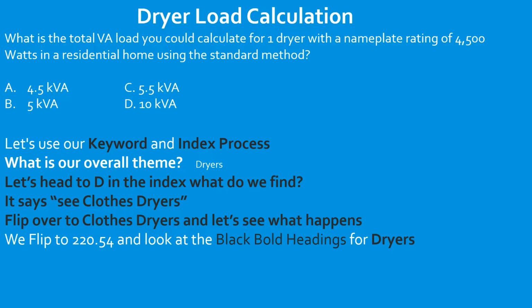So we flip over to 220.54. And if we notice, there's a theme happening here: any time it has to do with calculations, almost every time we end up back in 220, which we're going to talk about in the next slide. Now that we get there, we always look at the black bold headings and make sure we're in the right section. So when we get to 220.54, we read the black bold heading, we make sure that it's about dryers, it feels like we're in the right place, and let's go ahead and read the code now.